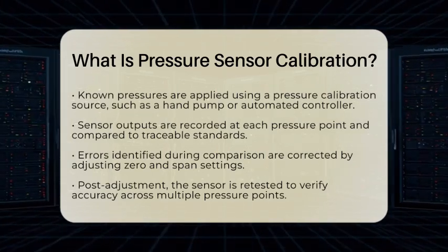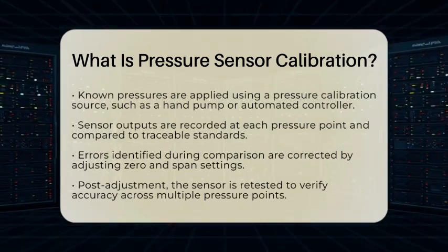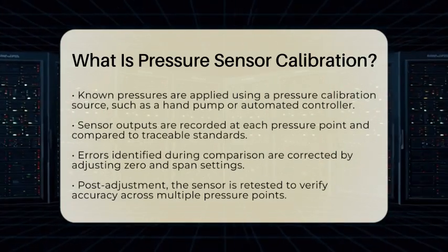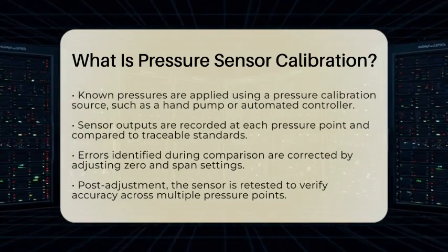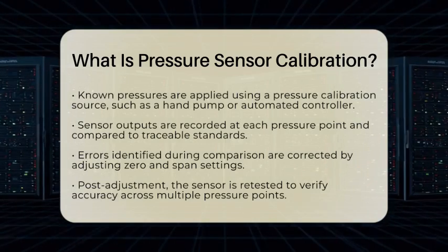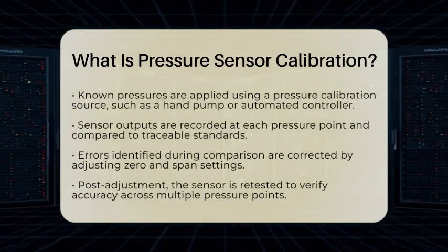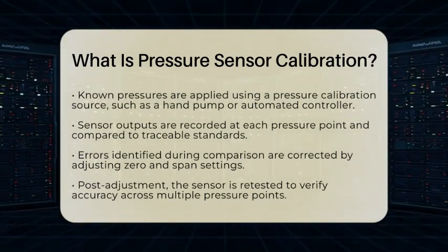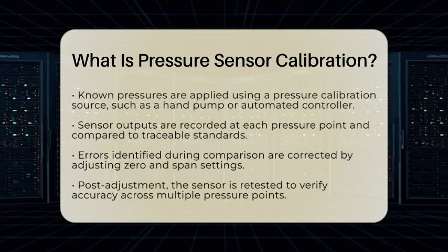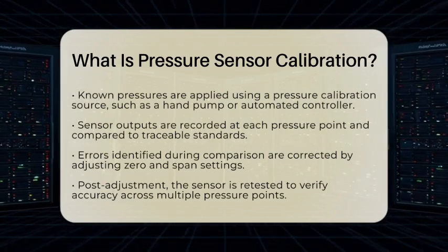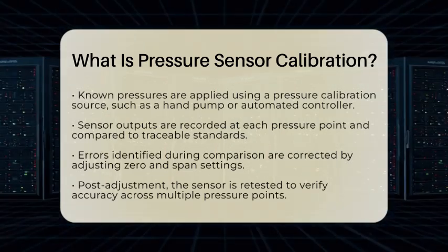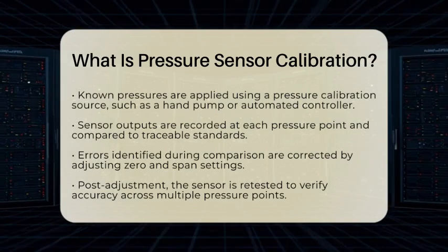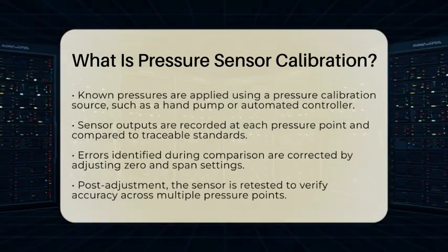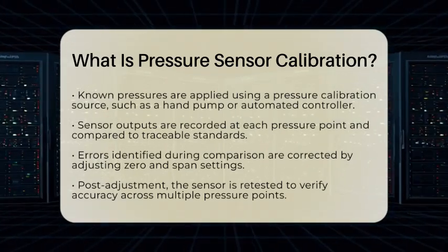The calibration process starts with applying known pressures using a pressure calibration source. This could be a hand pump or an automated pressure controller. These known pressures should cover the entire measurement range of the sensor. Next, the sensor's electrical output is recorded at each pressure point. These readings are then compared to a high-accuracy pressure standard that is traceable to national or international measurement standards.